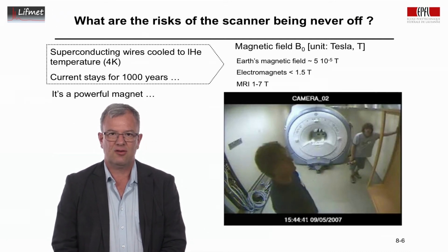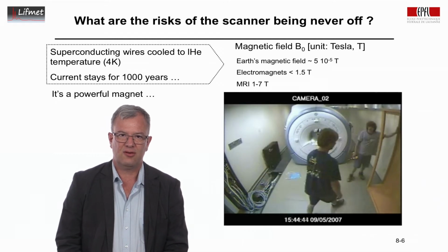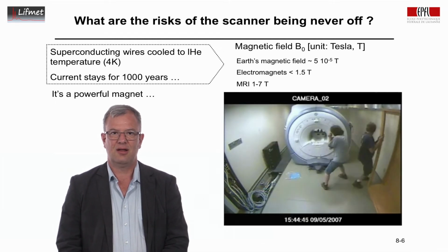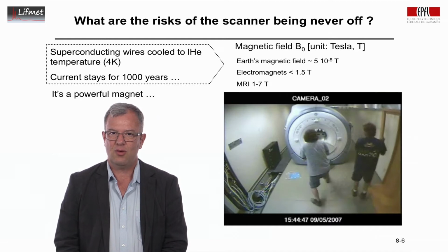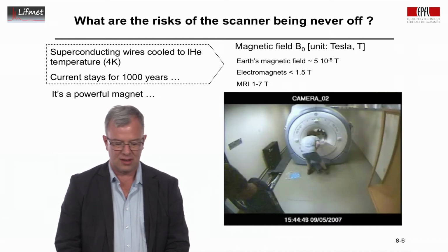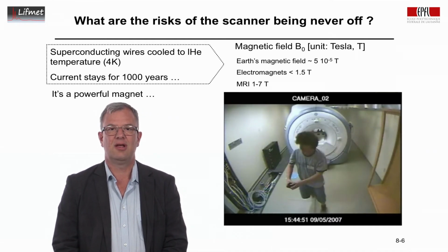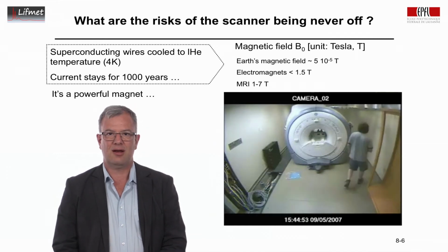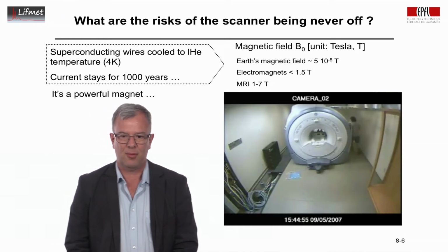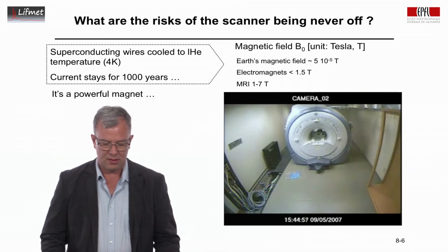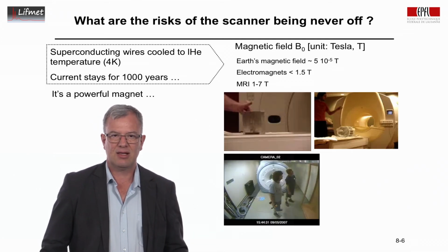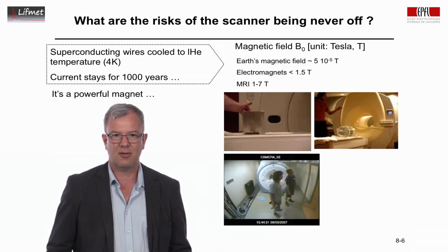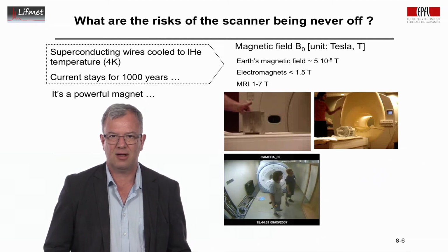As we are watching this video, you might notice at a certain time point that he is now without the drill, and as you're observing the two gentlemen, they are now looking inside the magnet. So what has happened? Well, the drill has most likely some ferromagnetic components to it, or at least a battery.